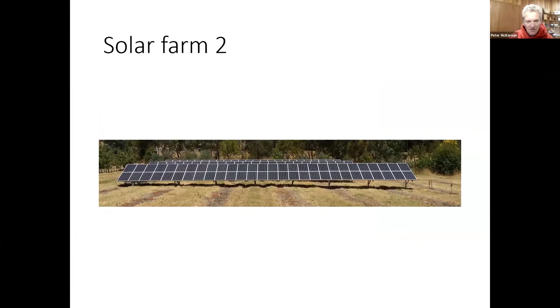To give you an idea of the system's capacity, we've got a 940 kilowatt hour battery - that's the gross capacity. We normally only use about 242 kilowatt hours out of that battery, to preserve it. We're hoping to get around 18 to 20 years out of this battery.